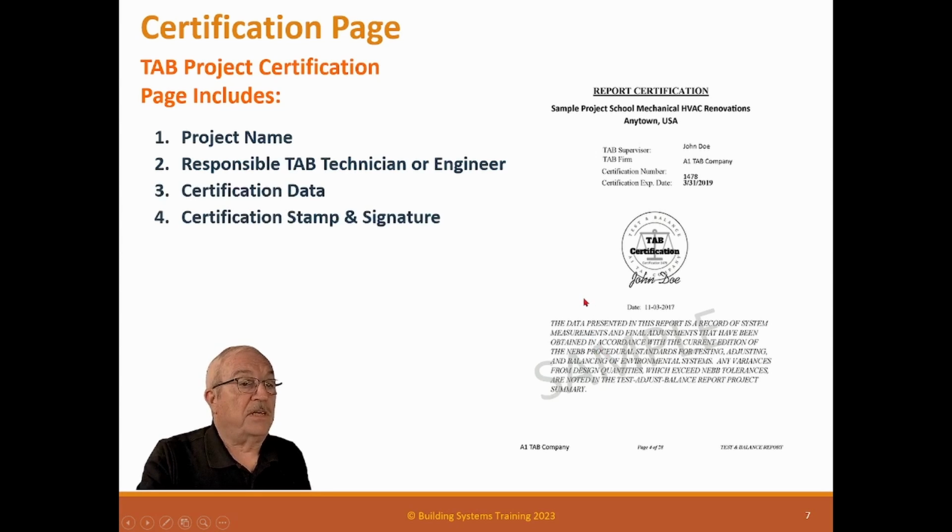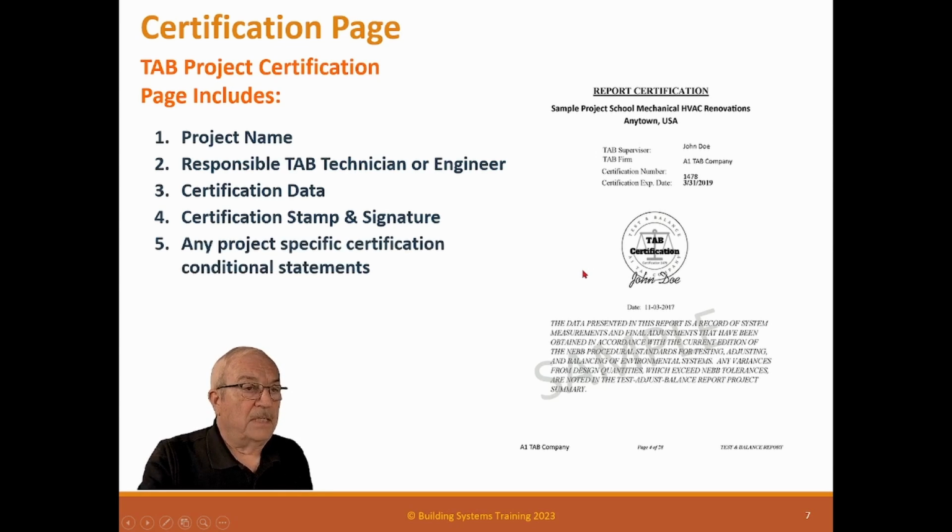The certification data has a stamp and signature. So this has actually been certified by someone who is a certified individual and not just some technician off the street. Any project-specific certification statements that are required, and all of us have our standard report pages, and again, a page number. Gotta make sure this hasn't been removed from the report.